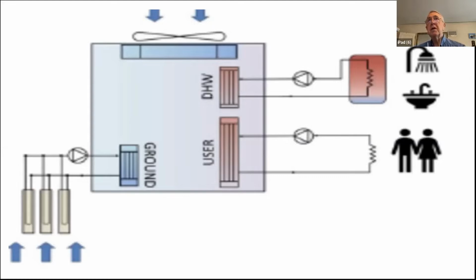I should explain also, DHW near the top in the box is domestic hot water. That supplies the hot water for your showers, your laundry, etc. And again, there are water pumps with the little circles and the triangles showing to the right. Where it says user, that means space heating and space cooling. It keeps the rooms in your house warm or cold, whatever you need. So basically, this has two sources, air or ground or water. And this is more versatile.